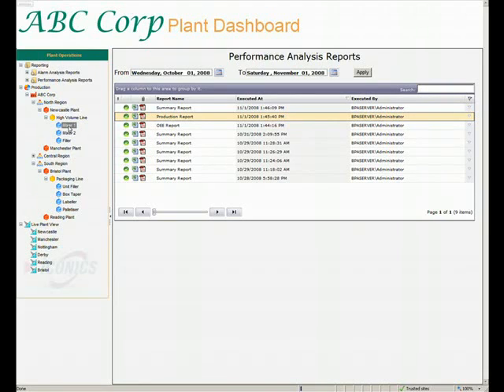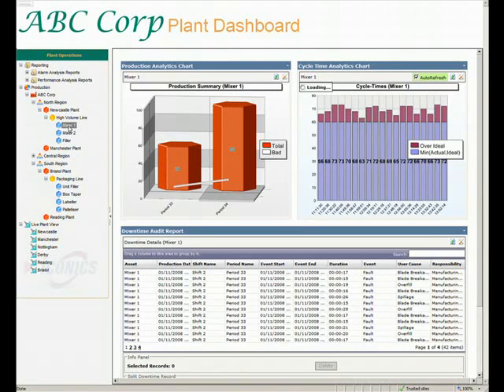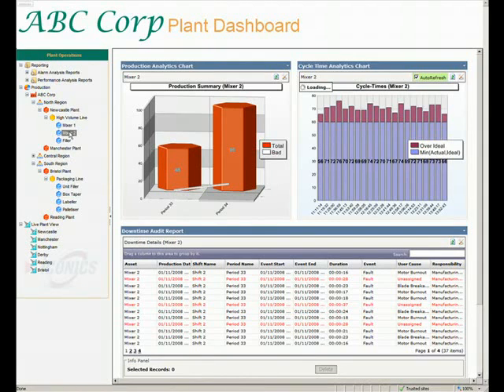Selecting a specific asset brings up a set of views and real-time components that display information relative to that asset. These views are actually also role-based, so depending on who accesses the system, a different view may be shown for the same asset. An example of this may be maintenance engineers and operators — the maintenance engineer would like to know the top five causes of downtime, while the operator wants to make sure he is within the cycle time limits.